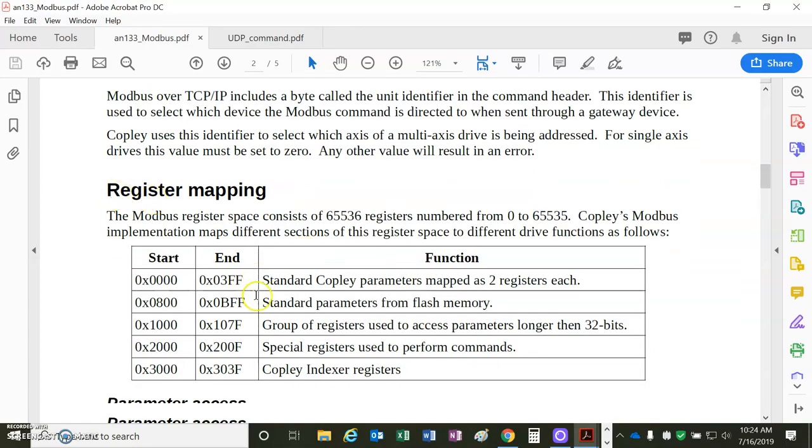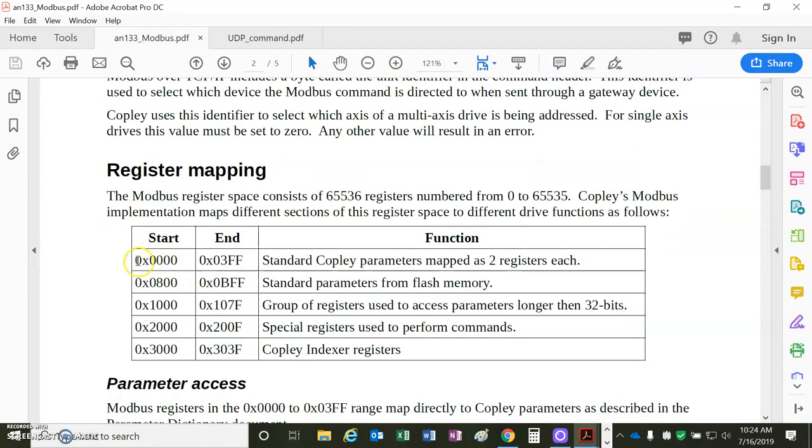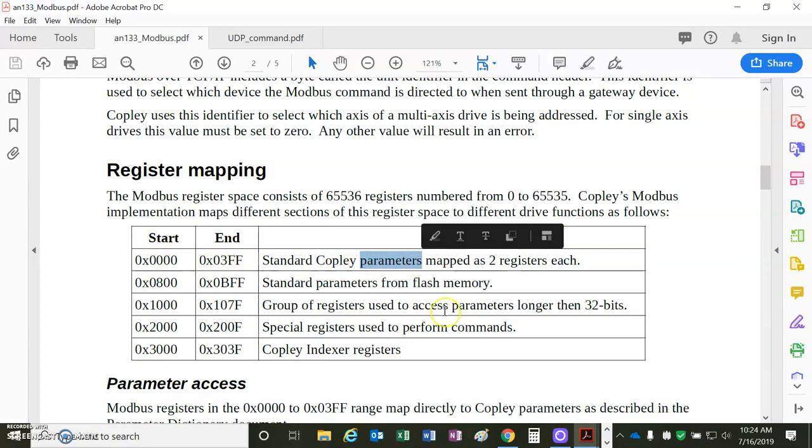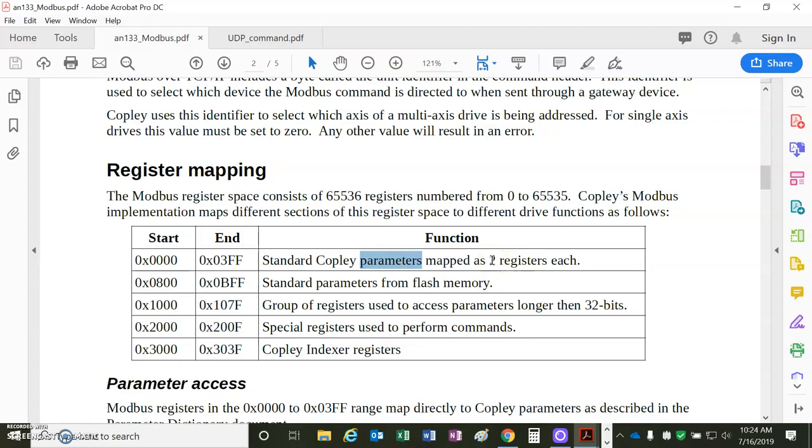The Modbus registers are mapped starting at 0. It correlates to the parameter dictionary. The parameter dictionary parameters are 32-bit typically, so you need two 16-bit registers.